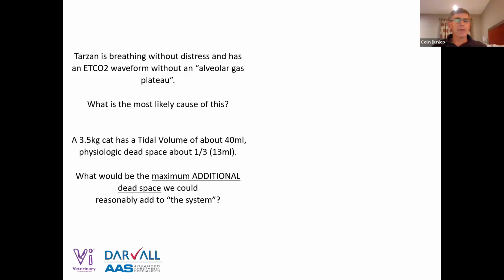So I'm watching these answers coming in, and I can see some people are picking some individual things and some people are saying all of the above. And I would say that all of the above could account for it. If you've got a cat with a high respiratory rate, you end up with a relatively small tidal volume, a small gas sample. So you end up with that inadequate sample, meaning we don't get some alveolar gas. If the cat has a non-rebreathing circuit with a high fresh gas flow and the fresh gas comes in at the endotrach tube connector, that creates a Venturi effect. It sucks some of the gas up the airway, giving us an inspired reading, but it also washes away the end tidal gas. So that could cause the problem.